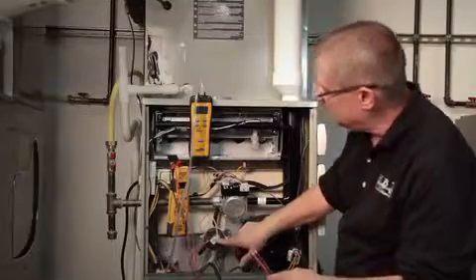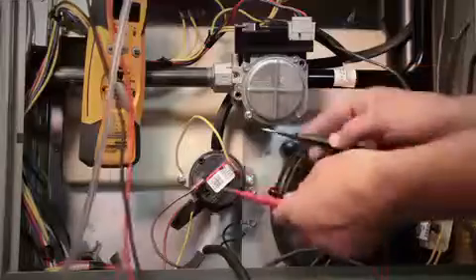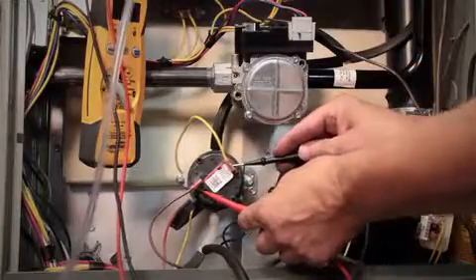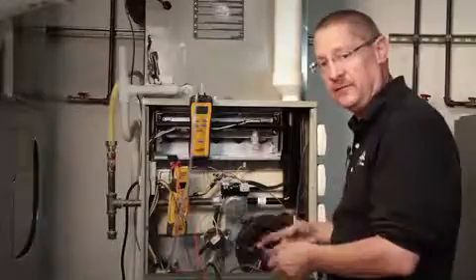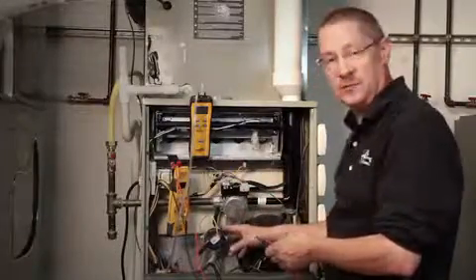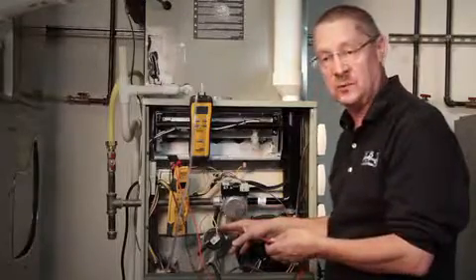If I am getting deep enough beyond the pressure switch rating, then I'm going to check for my voltage. Did the switch indeed close? If it closed, great. If it didn't, we've got a bad switch because we have deep enough vacuum to make the switch.